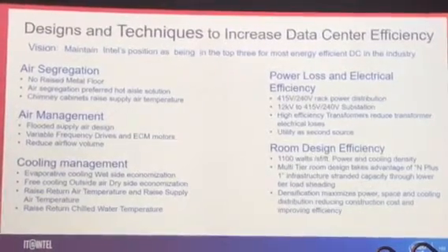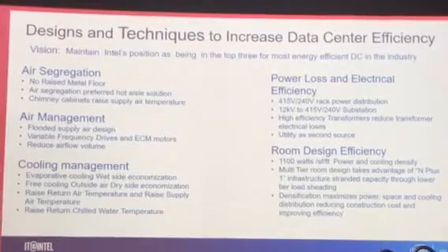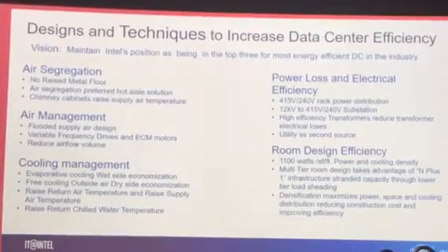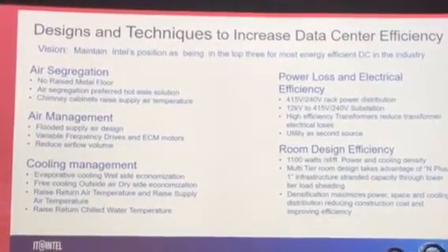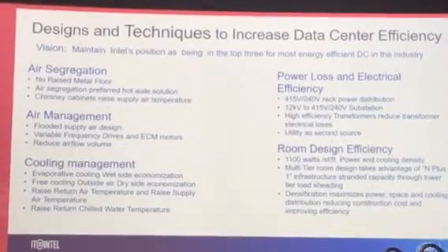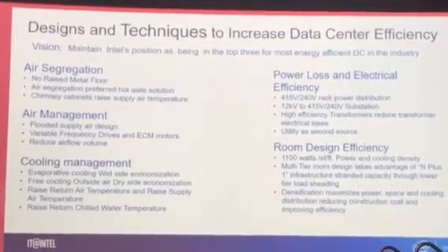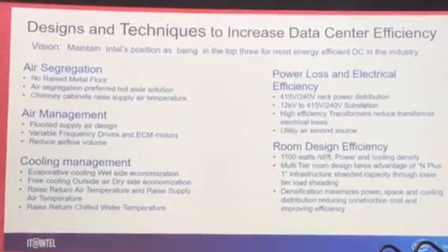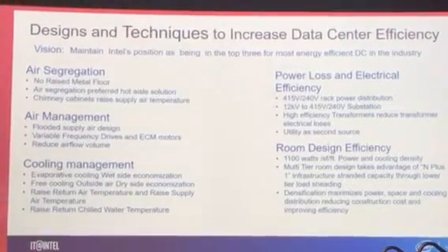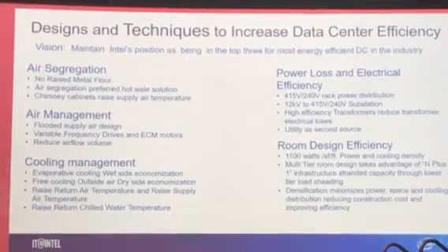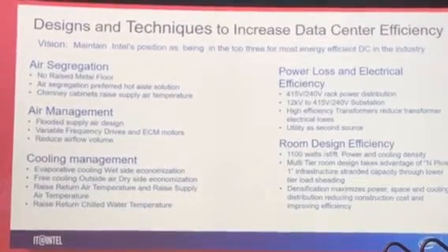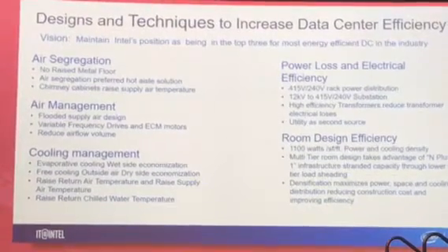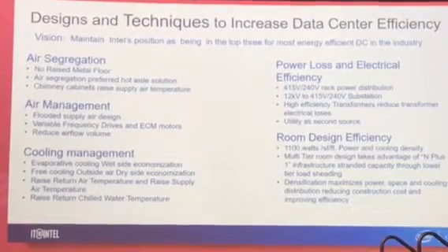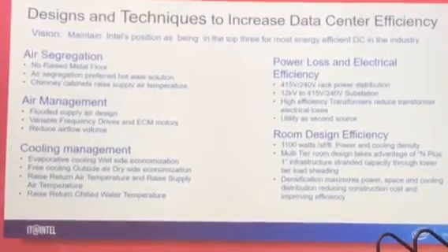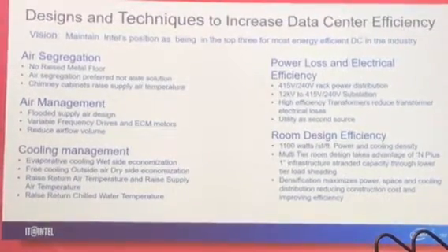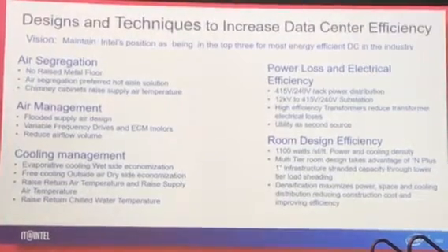The cooling management, you saw the 2, the wet side economizer also could be another one, the outside air and the closed couple cooling. We also raise the temperature. Again, we proved that we don't need to reduce the temperature to 70. This is important, and we're showing with Intel that the servers, the Xeon and the latest CPUs, can work with a high temperature without any issues.